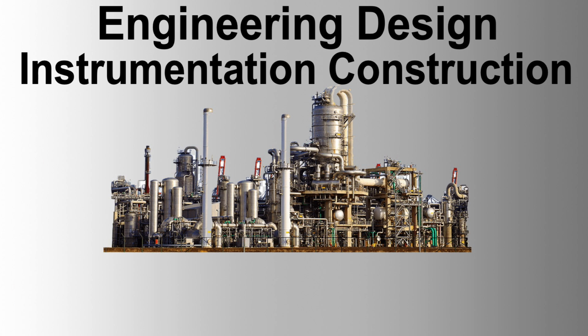Terminal blocks. Terminal blocks shall be of the type specified in the project documentation, suitable for the number of connections and current rating of the circuit. Terminal blocks shall be installed in enclosures that provide adequate protection from environmental conditions, such as dust and moisture. Terminals shall be clearly and permanently labeled to correspond with the project drawings and cable schedules.